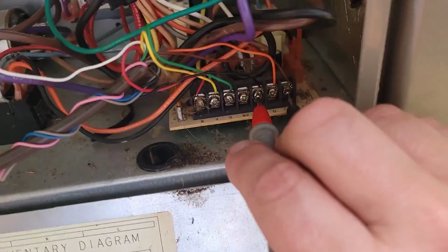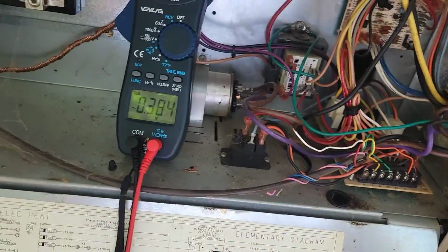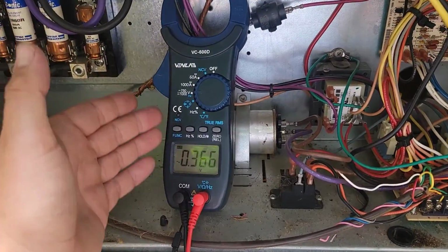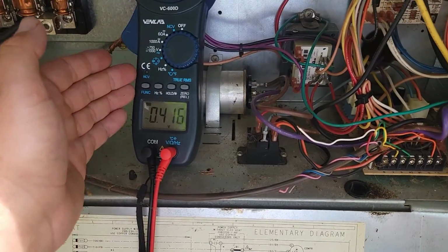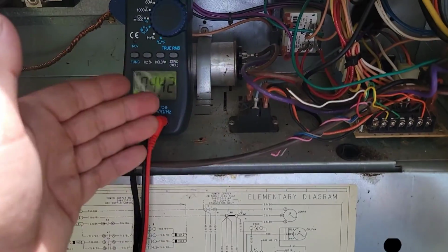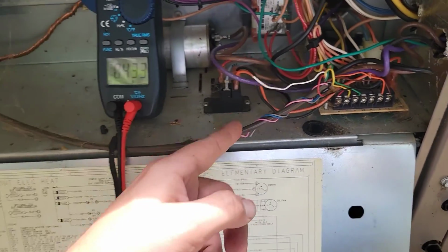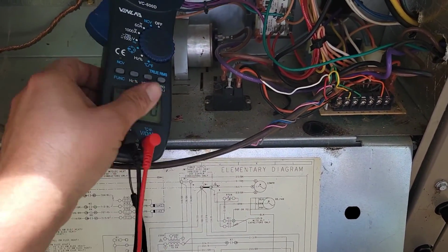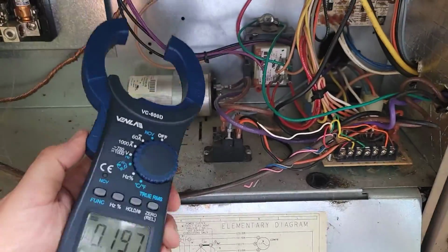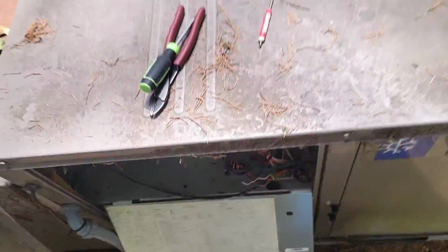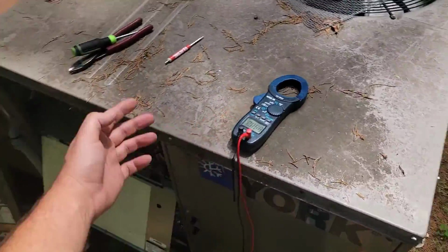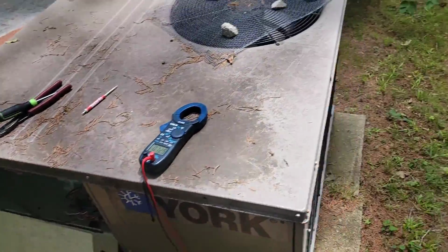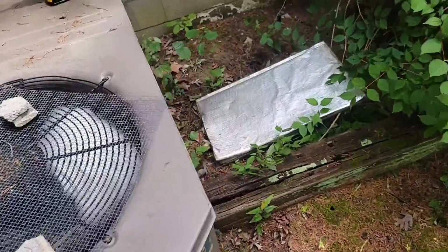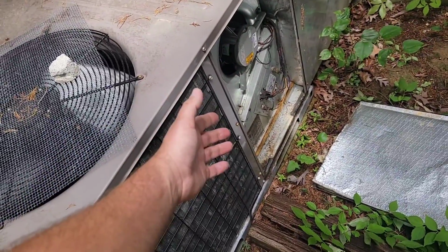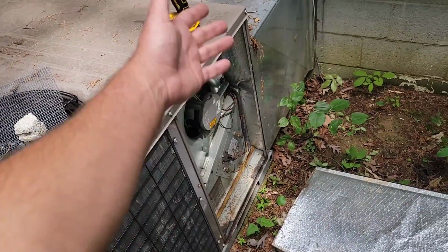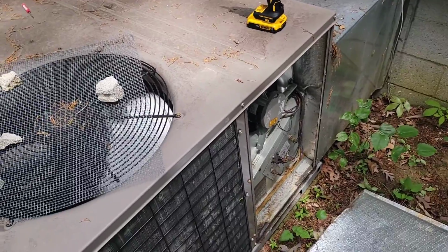Oh, and we've got 3 volts. So that means it's definitely a thermostat wire problem. It's not a thermostat issue. I'm gonna try another wire, and if I can't get another wire to work, then I'm gonna replace the thermostat wire, okay? And that's how I'll fix this issue. So I guarantee you that it was energizing the heater kit, and the heater kit is what was causing all the heat to be blown into the house, and that's what was happening.